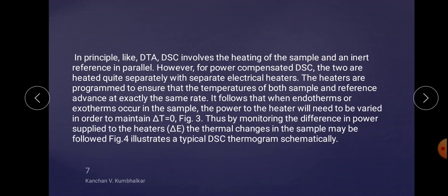But in DTA, we put the sample and the reference in the same chamber and give heat, programmed continuous and constant to both reference and sample, both heated in the same heater chamber. But in DSC, with power compensation, the two are heated quite separately.